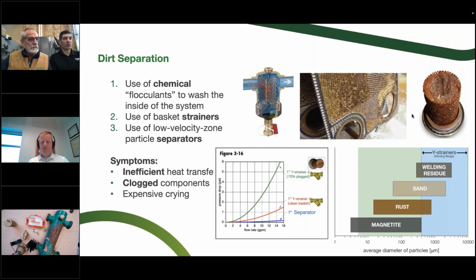And then let's say you have a basket strainer, there's still debris getting into a circulator, into a heat exchanger of a boiler. You can go with the tighter mesh of that strainer, but you're going to make this worse. That's going to be even more pressure drop if you get to a finer mesh on a Y strainer to catch those smaller pieces rolling around in the system, and it's going to plug quicker. So that's why the primary dirt separator is the best place to catch that stuff.